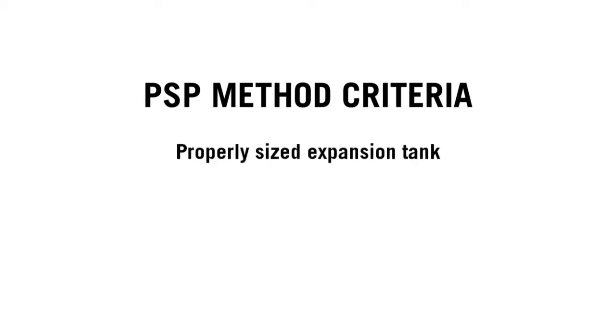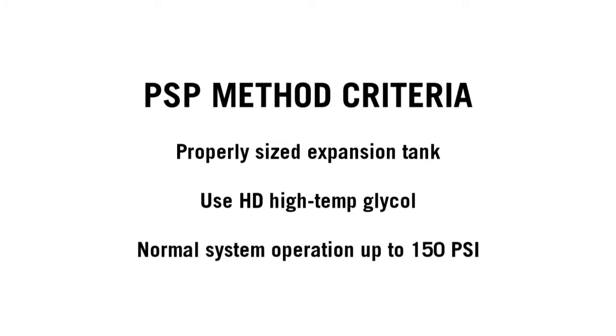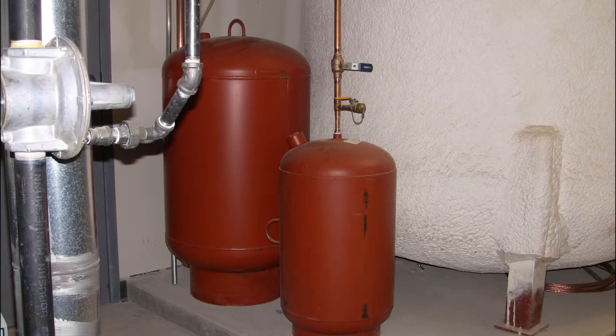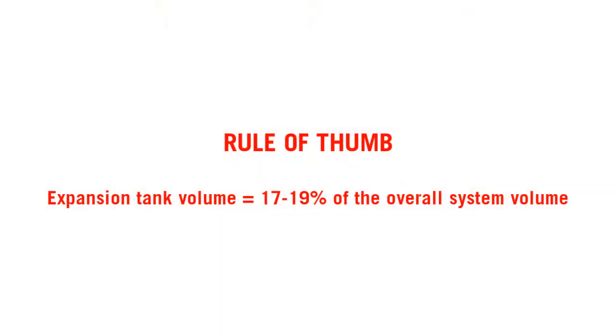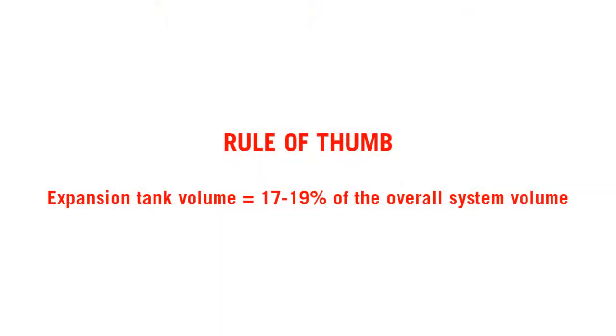To properly use the PSP method as a form of stagnation protection, you must properly size your expansion tank to allow for controlled system pressure behavior, use HD high-temperature glycol, and allow normal system operation at pressures up to 150 PSI. Expansion tanks are sized according to the total volume of fluid within the solar loop. A typical rule of thumb in residential systems is to use 17 to 19 percent of total system volume for your expansion tank volume.